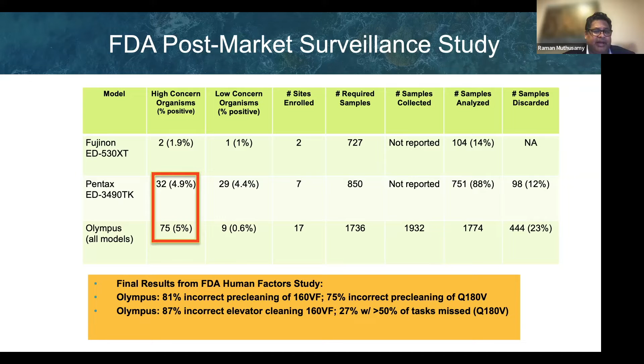In addition, a human factor study looking at how well people follow the steps of both in-room pre-cleaning as well as manual cleaning showed that 75 to 80% of the pre-cleaning steps were done incorrectly, and that at least 7 out of 8 times, there was at least one elevator cleaning step done incorrectly, and in about a quarter of the cases, half the steps were done incorrectly in terms of manual elevator cleaning. So I think these devices are somewhat complex to clean.